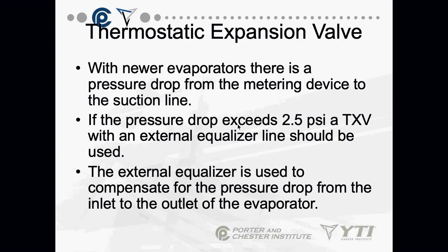The equalizer is used to compensate for that pressure drop, because again, our evaporator pressure is part of our forces that open or close the TXV. 2.5 psi is not a whole lot. It's a very insignificant amount, but it does make a difference in that TXV.